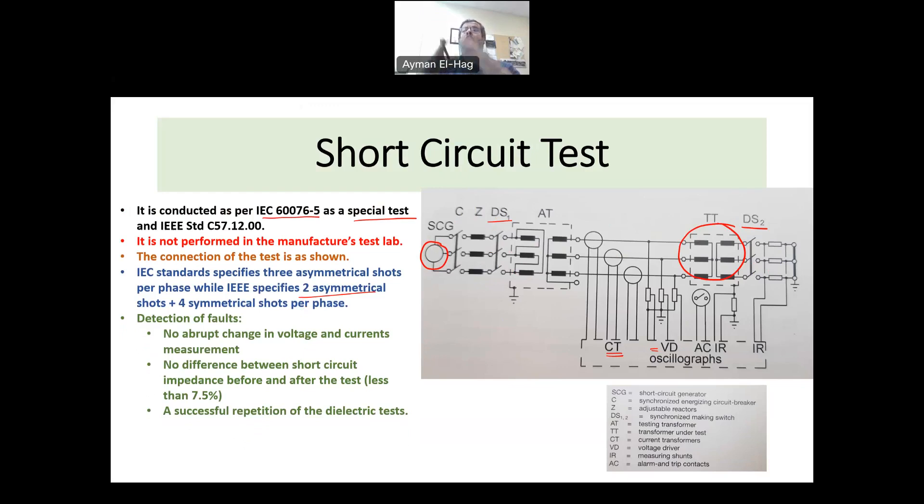Usually, we also open the transformer to see what physical damage occurred. Because usually there is physical damage happening inside the transformer, but you want to see how severe the damage is and whether it affects the routine dielectric test, the short circuit impedance or not, to decide if the transformer passed or did not pass the test. So that is the special test that is used to make sure that your transformer can withstand a short circuit if it happens in the field.